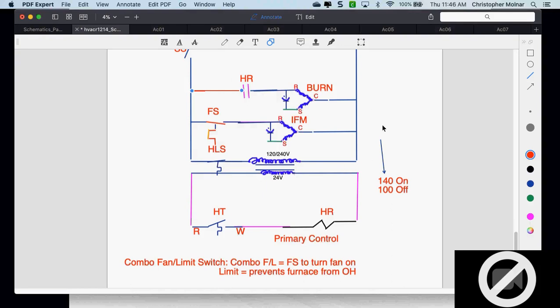Okay. By the way, when you reset a digital thermostat, there's a delay before the heat comes back on. Okay, and a lot of times we do use the high limit switches, especially on boilers, as an operating control. So we try not to do this anymore. You still see this in books. This is why I want you to be aware of this whole problem. You still see this whole thing in some of the books you'll look at. But remember, a lot of the books you're reading, a lot of the books on oil burners, were actually written before we started having a lot of digital controls. Digital controls need a constant source of power. Okay? So when you look at oil burner controls, when you look at these controls, I want you to remember that if this thermostat is digital, you've got to keep power on that thermostat.